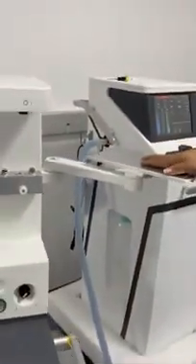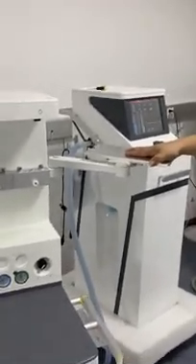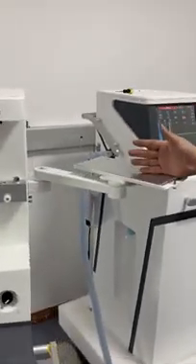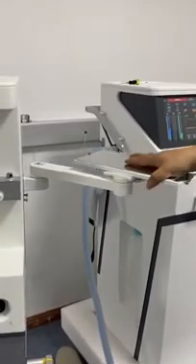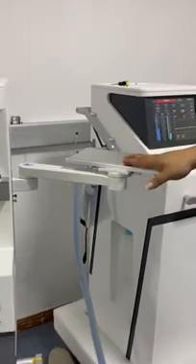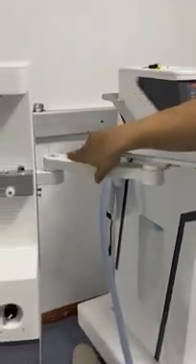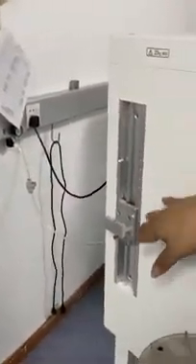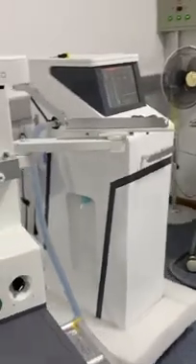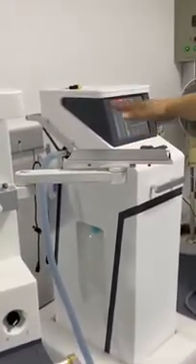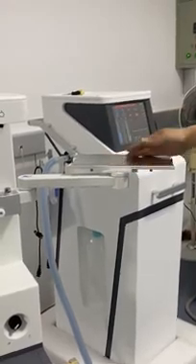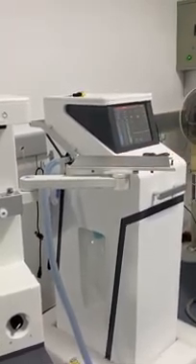Here is the patient monitor holder. For example, if you want to equip the machine with a patient monitor, or maybe an anesthetic monitor, then we will have this frame. The frame can be mounted on the right side of the anesthesia machine, or we can also put it here. It depends on your decision, because in different hospitals the position of the machine relative to the bed is different, so you can choose. Then we put the patient monitor on the holder, and it is very easy to tighten with screws.